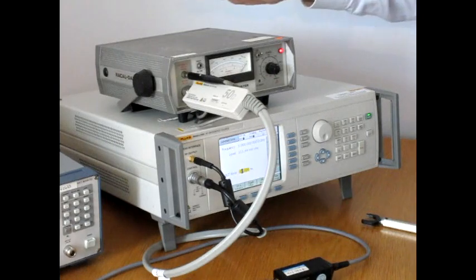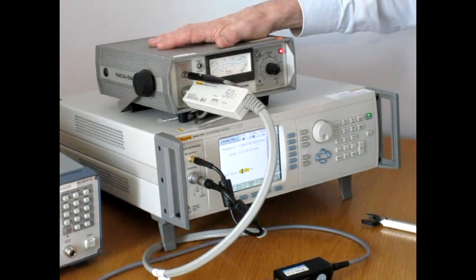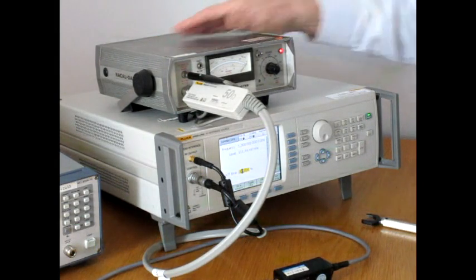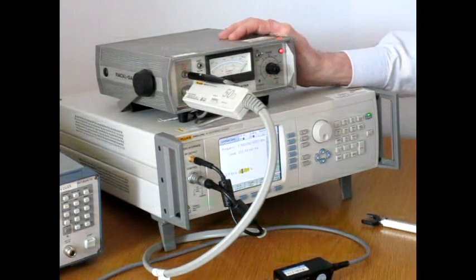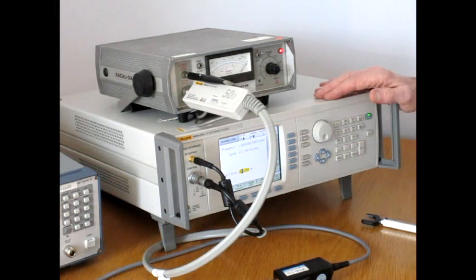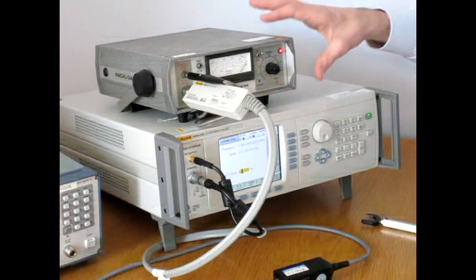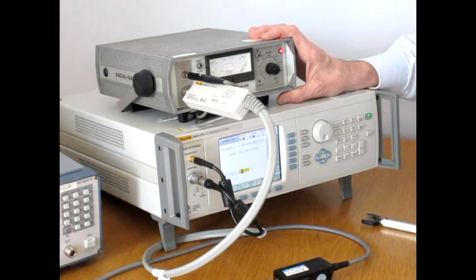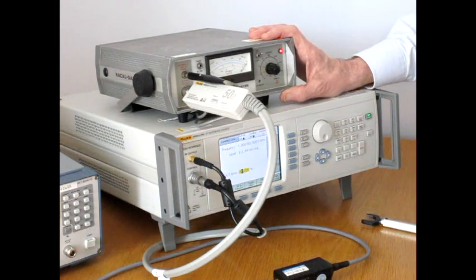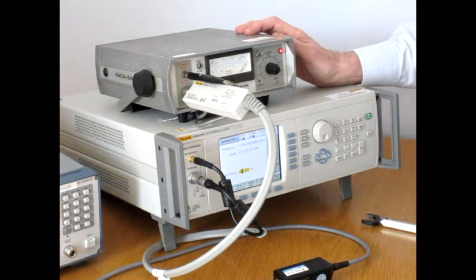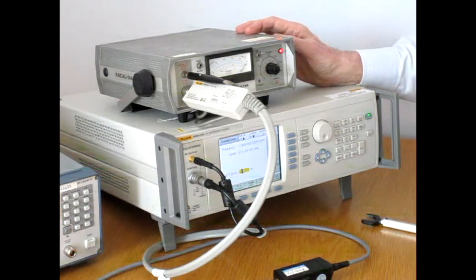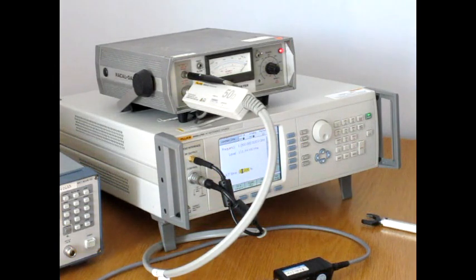And incidentally, we have an instrument here which is specified for frequencies down to 10 kHz, but the 9640 is ideal for other instruments with lower frequency ranges because its frequency range goes down to 1 millihertz. So we can easily calibrate other RMS voltmeters, for example, RMS voltmeters with frequency responses well down into the audio frequency range, with its very wide frequency coverage from 1 millihertz up to 4 gigahertz. It's an ideal, simple and easy to use solution for the calibration of RF millivoltmeters.